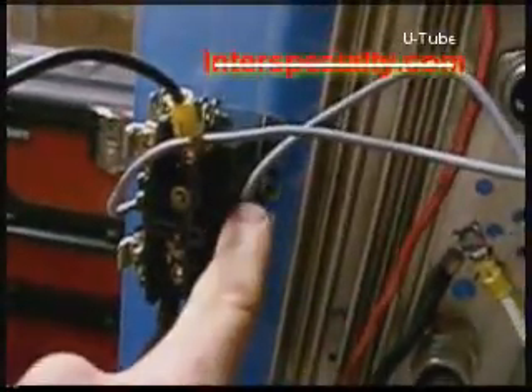Your low voltage transformer has two output wires. One wire will connect directly to the coil on your relay and one to the coil on your contactor. The other low voltage wire then connects into your torch low voltage wire, which goes to the trigger of your torch. When it's pulled, it'll then allow current to flow out the other wire, which you will then connect to the remaining coil contact on your fan relay and your contactor.